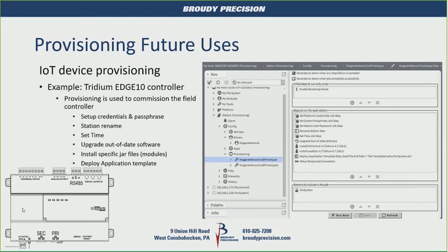It's obviously software. Its license is limited for the number of devices it can talk to, so you can't use it as a Jace. Basically you're going to have one field device that can connect to it. Yeah, it's a controller, not a Jace. So you're going to connect on the Niagara? Yes. Okay, so you have to pull in Niagara points. Correct.